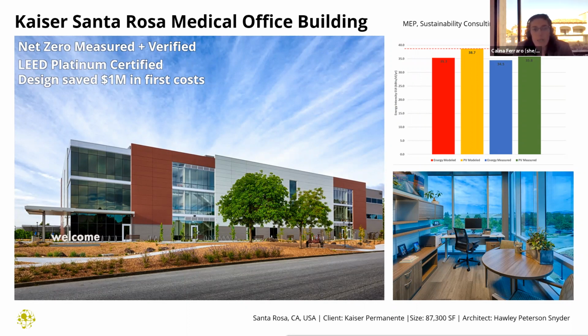One really good example of that was the way we zoned our mechanical systems. By having individual envelope exposures or similar uses on a single system, we eliminated the need for reheat, which in a medical building with a lot of constant volume spaces is really inefficient if you have to cool the air and then heat it back up again. By eliminating the reheat, we eliminated the entire heating hot water hydronic system.